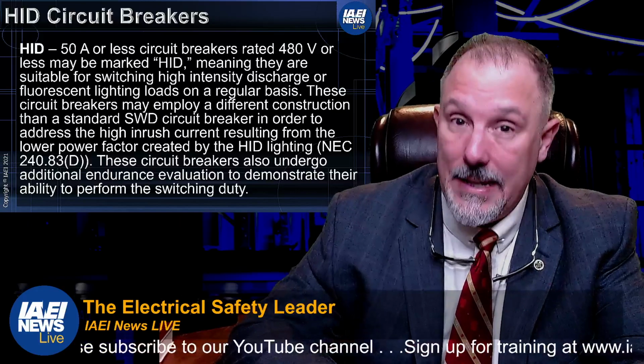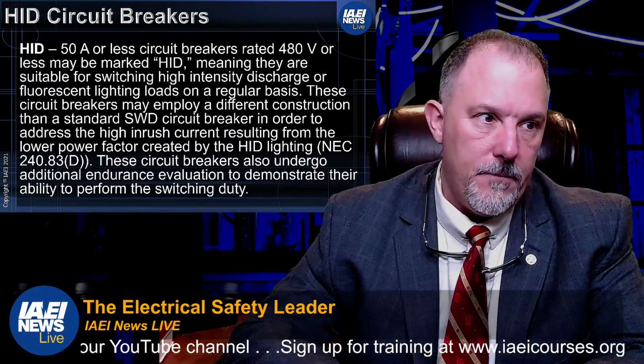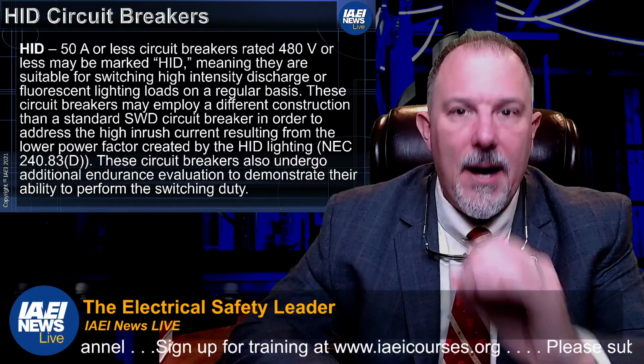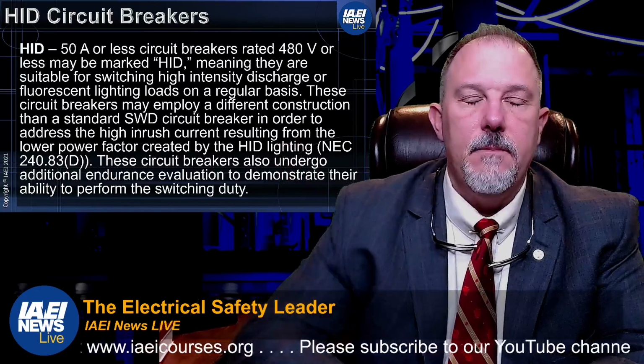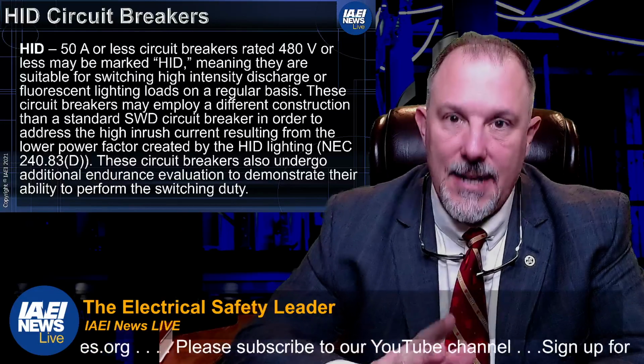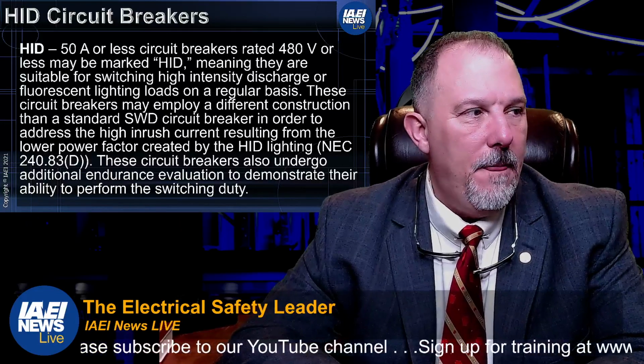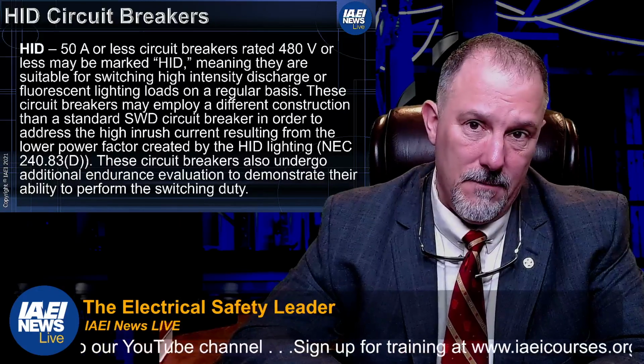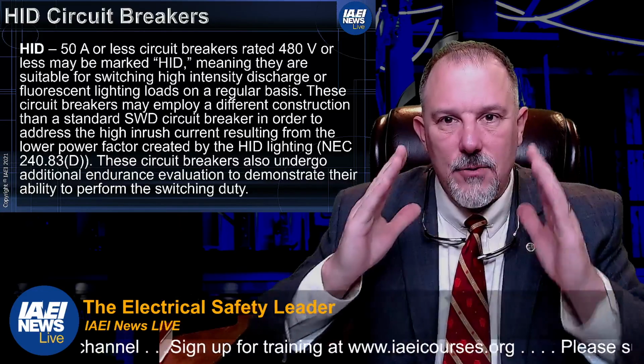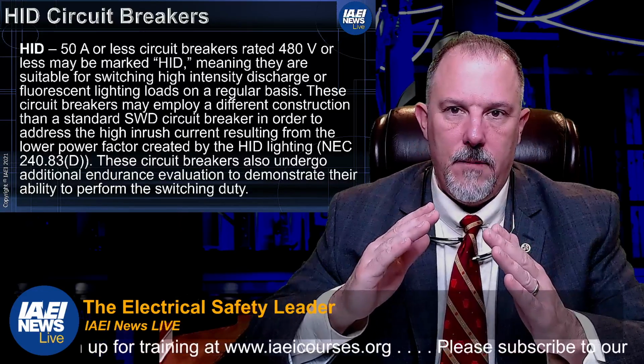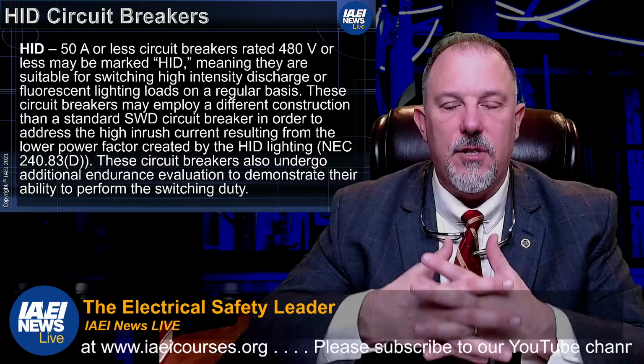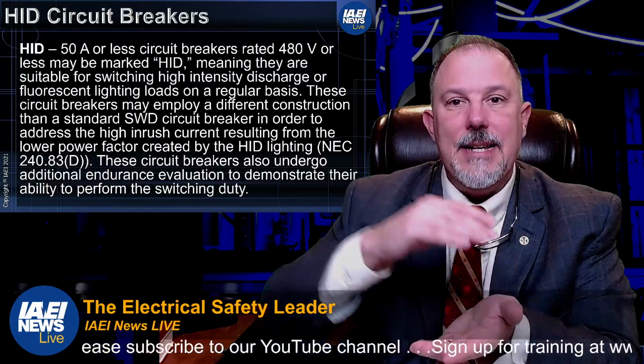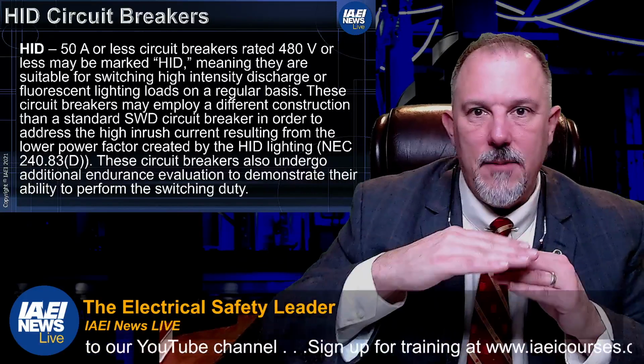Years and years ago, it was all incandescent bulbs, right? And we had unity power factor. When we started coming out with other technologies like fluorescent, LEDs, HID, etc., those devices don't have unity power factor. What does that do? That's a phase angle difference between current and voltage. When I switch these technologies, that switching angle, I can hit that current when the voltage is at a minimum and the current is at a peak, or when the current is at a minimum and the voltage is at a peak.